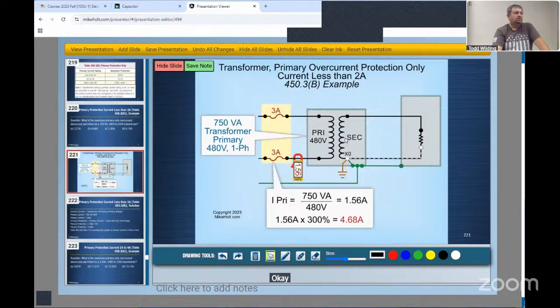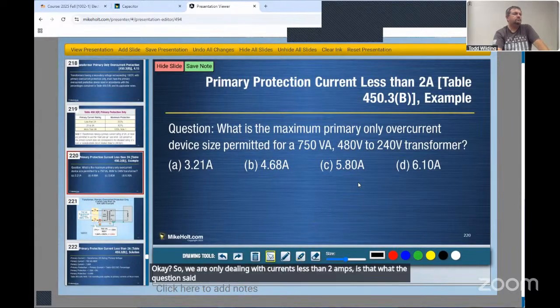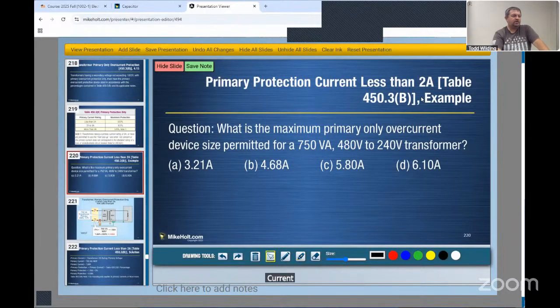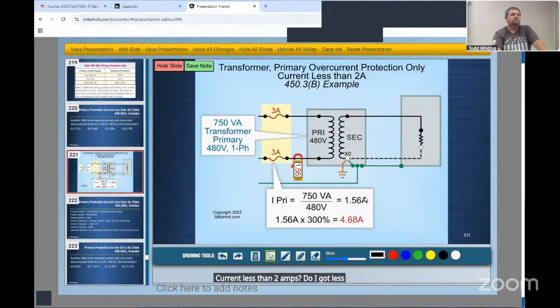Okay. So we are only dealing with currents less than 2 amps. Is that what the question said? Current less than 2 amps. Do I have less than 2 amps? Absolutely. So going to that table, Table 450.3(B), do I multiply it by 125, 167, or 300?